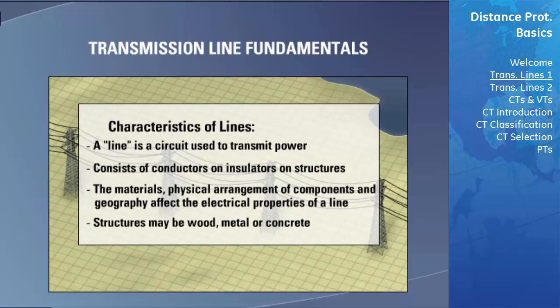For example, wood pole lines tend to have a much larger zero sequence impedance than a steel tower line. Since this impedance is much larger, the total impedance to ground is also generally larger, which may cause problems for a ground distance element. In a case like this, you may need to change your protection scheme to include an additional directional ground overcurrent element to find an effective solution.